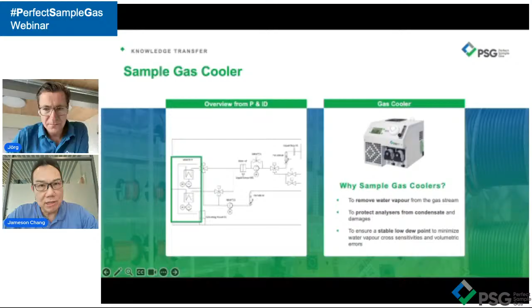Therefore, having a dew point is combined with the washout of certain gases, and combined with the T90, the response time, especially for calibration. With all these three together, dew point, washout, and T90, we classify two families. One family we call the emission monitoring cooler, and the other is the process cooler.